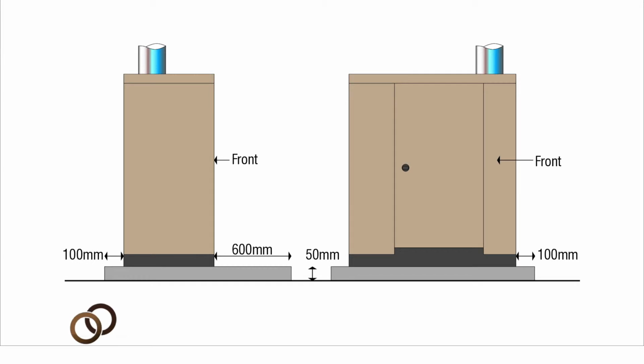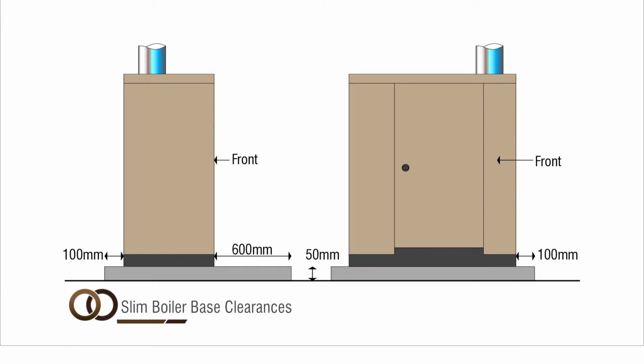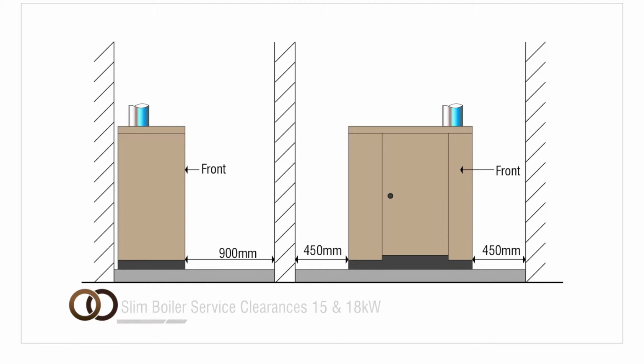The base needs to be 50 mm high and should project a minimum 100 mm beyond the sides of the boiler and at least 600 mm to the rear and front of slim boilers. On the 15 and 18 kilowatt models, the installer must leave enough space so that the user and service engineer can access the boiler routinely. This means leaving at least 900 mm at the front of the boiler and 450 mm at either side.